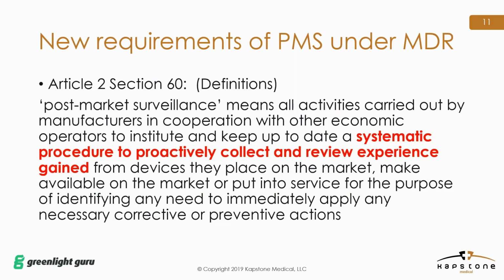So now to get down to the nitty-gritty of the regulation. I think it's important to understand how post-market surveillance is actually defined in the medical device regulations, as this definition is what drives the further requirements within the regulation. Article 2, Section 60, which is the article with the definition, states post-market surveillance is defined as all activities carried out by manufacturers in cooperation with other economic operators to institute and keep up to date a systematic procedure to proactively collect and review experience gained from devices they place on the market, make available on the market, or put into service for the purpose of identifying any need to immediately apply any necessary corrective actions.